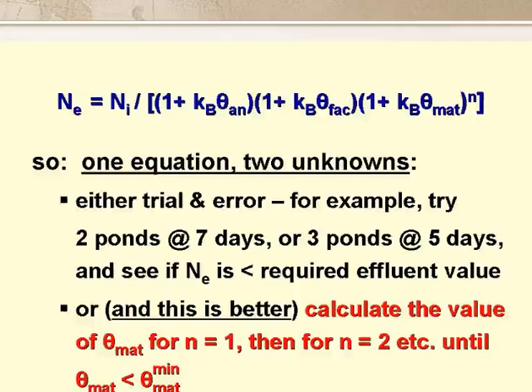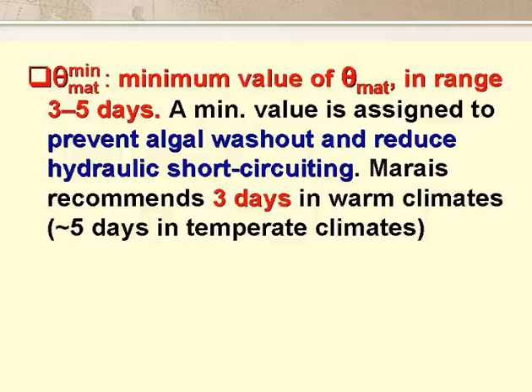So we have one equation with two unknowns. We can solve it either by trial and error, or — and this is better — by calculating the value of theta mat for N equals 1, then for N equals 2, and so on, until theta mat is less than theta mat min, the minimum value of theta mat. A minimum value of theta mat is used in order to minimise hydraulic short-circuiting and to allow sufficient time for the algae to multiply. Theta mat min has a value in the range 3 to 5 days — generally 3 days in hot climates and 5 days in temperate climates.